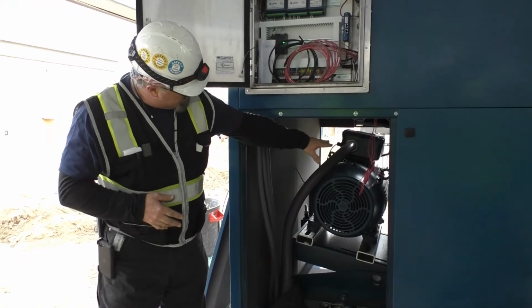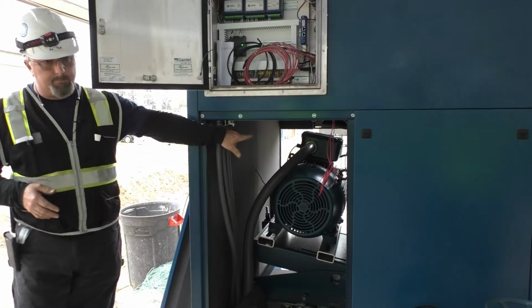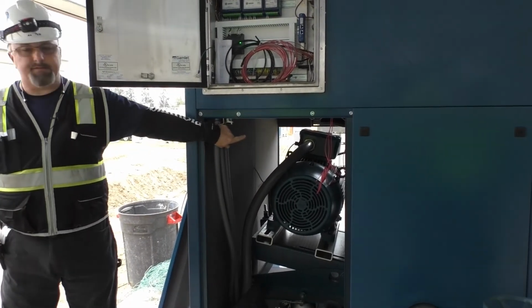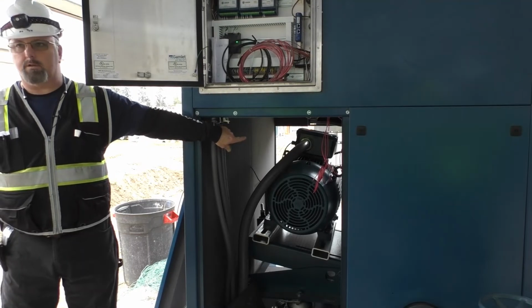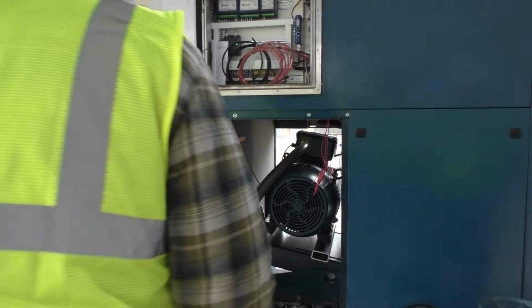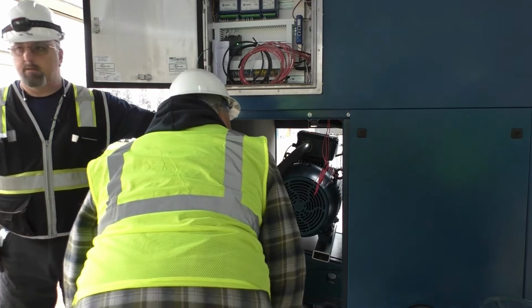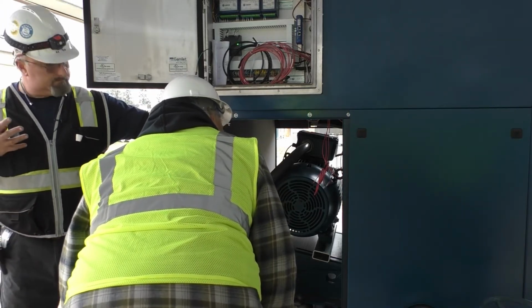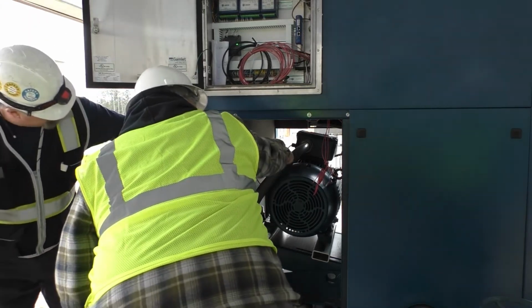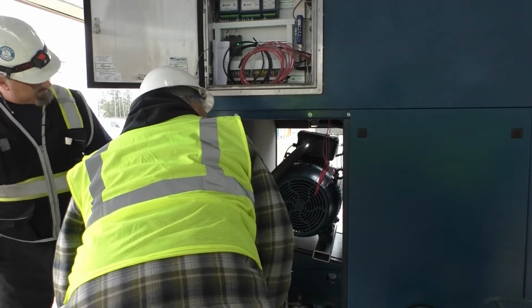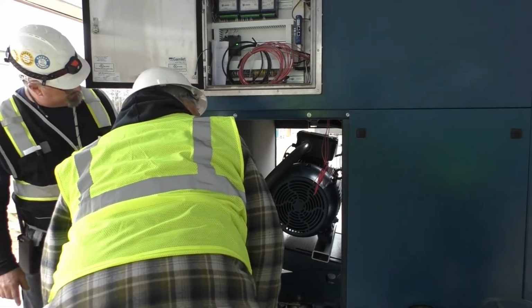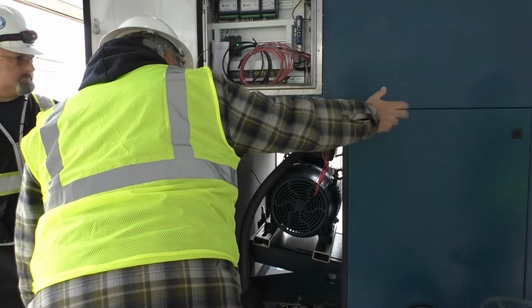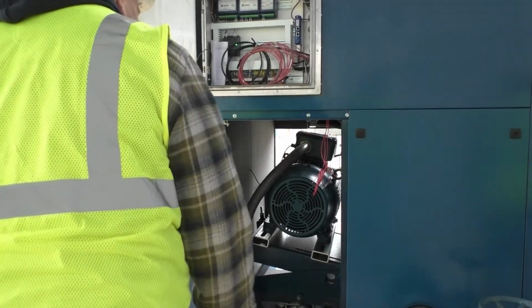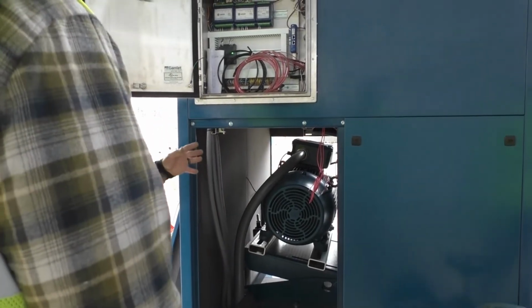Now, inside here, if you want to come up and look, there's a brass ring. That is your oil level sight glass that I was referring to on the stage. There's one on all 4 corners. The other 2 are on the opposite side against the wall. There is no cover over there. To see those, you climb in.